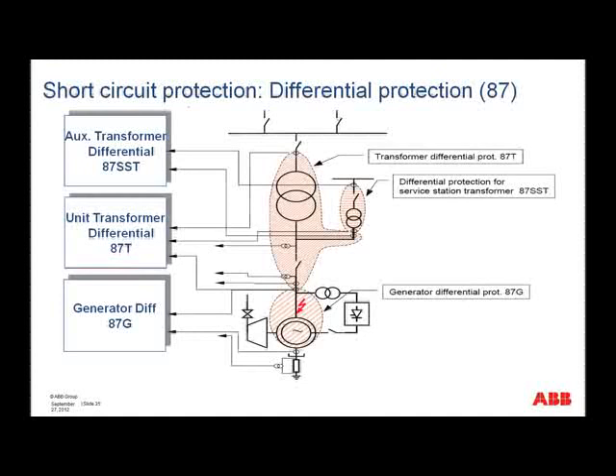So here we just have a picture that shows the different zones of protection for the different differential functions. So we have the 87G across the generator. So we would have CTs here and CTs here defining the zone of protection for this. Then what is shown here is actually a separate 87T, and the zone would be from this CT here to the CT down here to the CT over here. Of course, if this wasn't an 87T, but it was an 87O, as shown in most of the other slides, then this would not be the boundary CT, but the boundary would include down to here, and that would be the zone. And here we then have the zone for the differential protection for the auxiliary transformer.